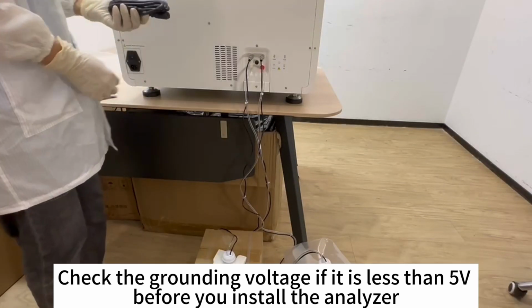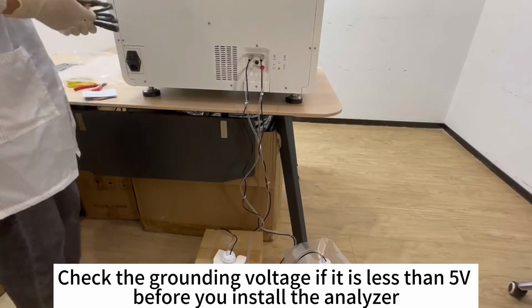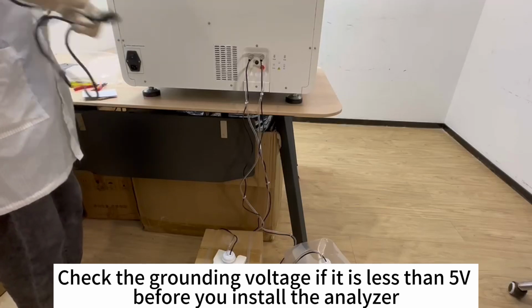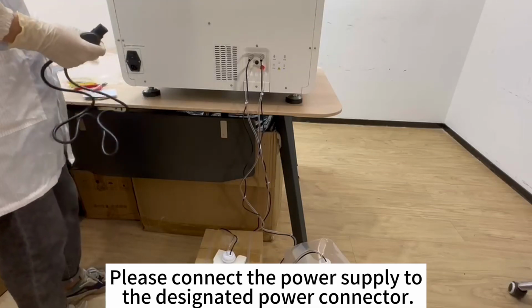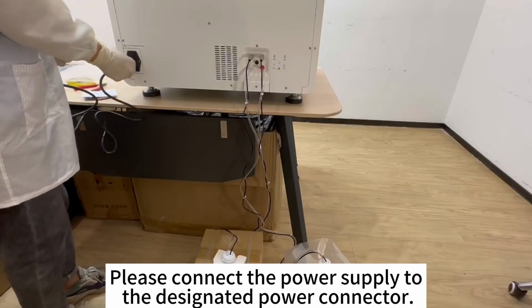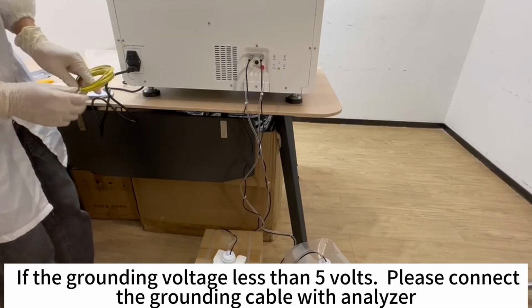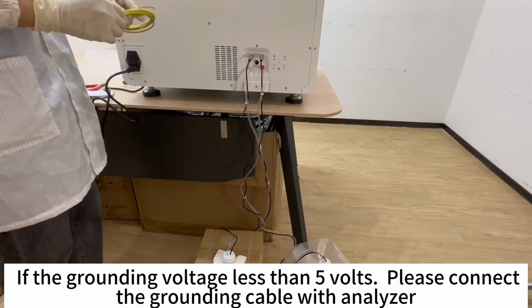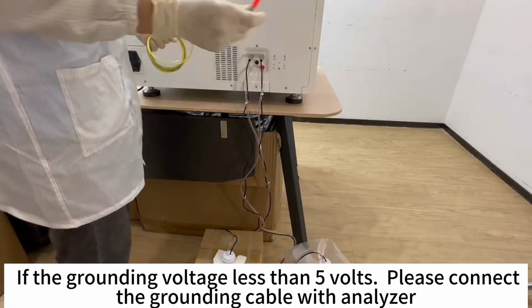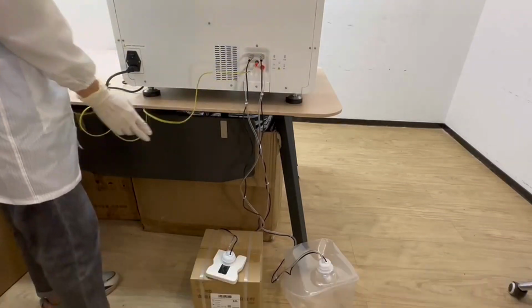Check whether the grounding voltage is less than 5 volts before you install the analyzer. Please connect the power supply to the designated power connector. If the grounding voltage is less than 5 volts, please connect the grounding cable to the analyzer.